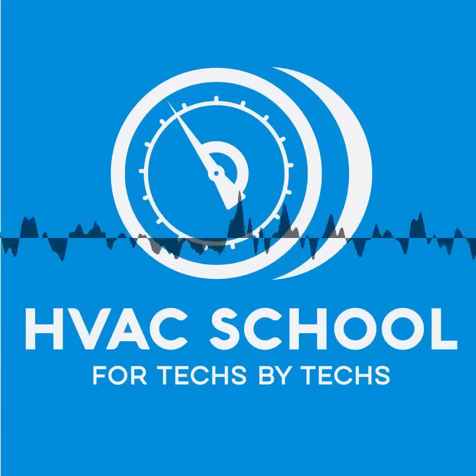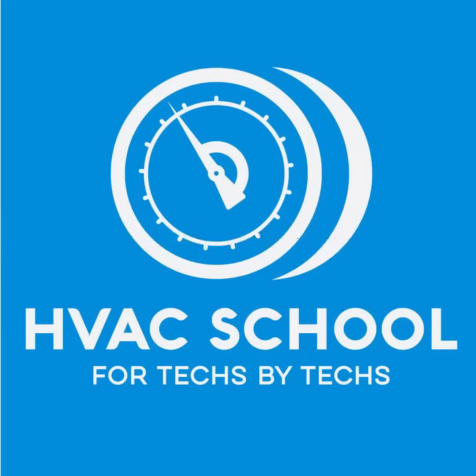So there you go. That's what we're doing today, but now we're going to go back and talk to Eric Melly. One thing I wanted to mention real quick is it is tough to get readings, and I'll actually talk about that right now. What kind of readings can you get off of these air handlers? That's the challenging part a lot of times, because you might not have the access to get the readings you need. It probably comes back to cost and to how well you tend to need to insulate the piping. But to have test ports, now you're compromising your insulation, plus you have to add the test port, plus will anybody ever be able to find it once it's buried in insulation?